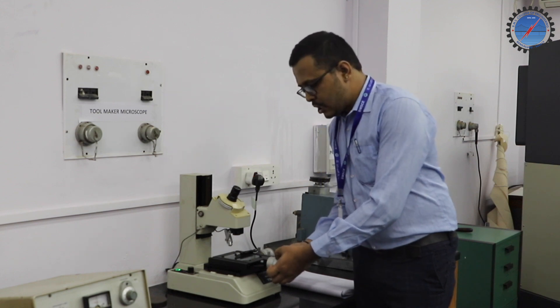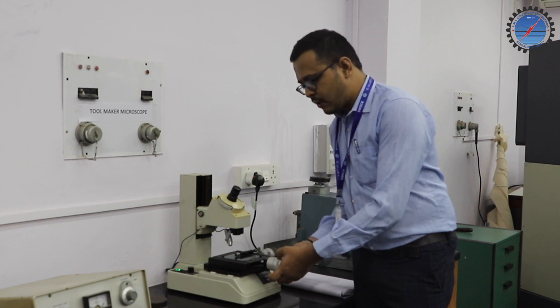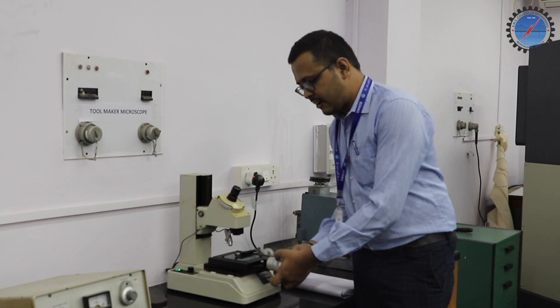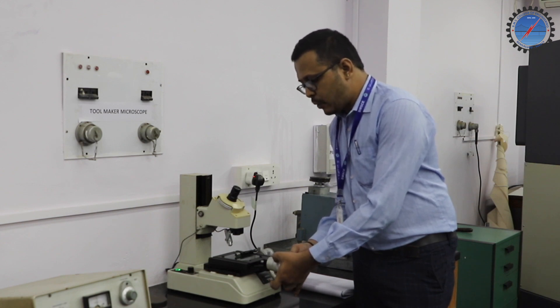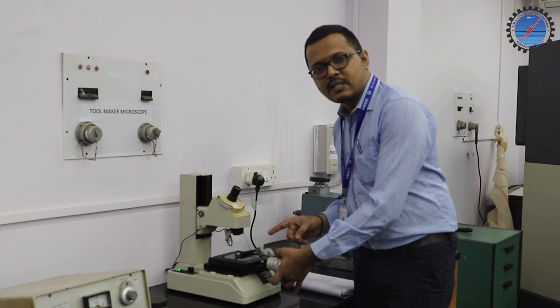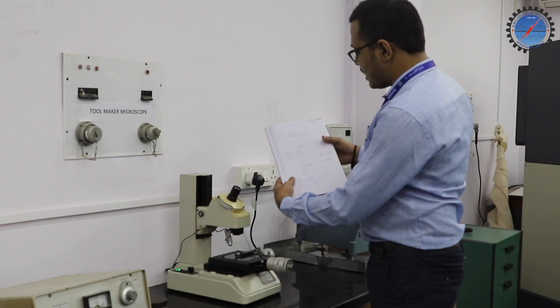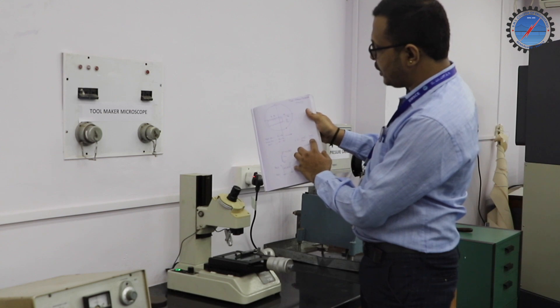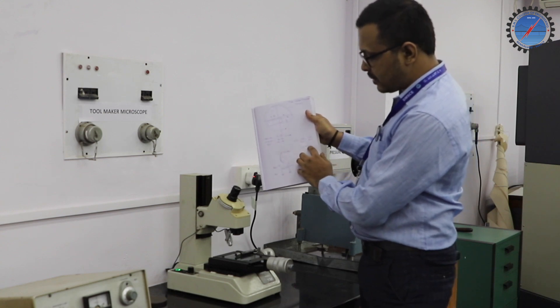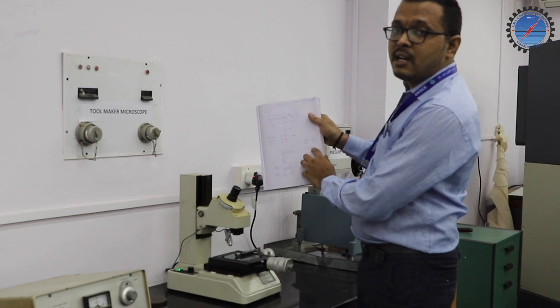Continuing: 0 to 10 is 20 divisions, 0 to 50 is 100, 0 to 90 is 180, and completing the full rotation gives one complete division of 1 mm, divided by 200 total divisions. Therefore the least count of the linear scale is 1 mm divided by 200, which equals 0.005 mm — that is 5 microns. That is the smallest measurement we can make.